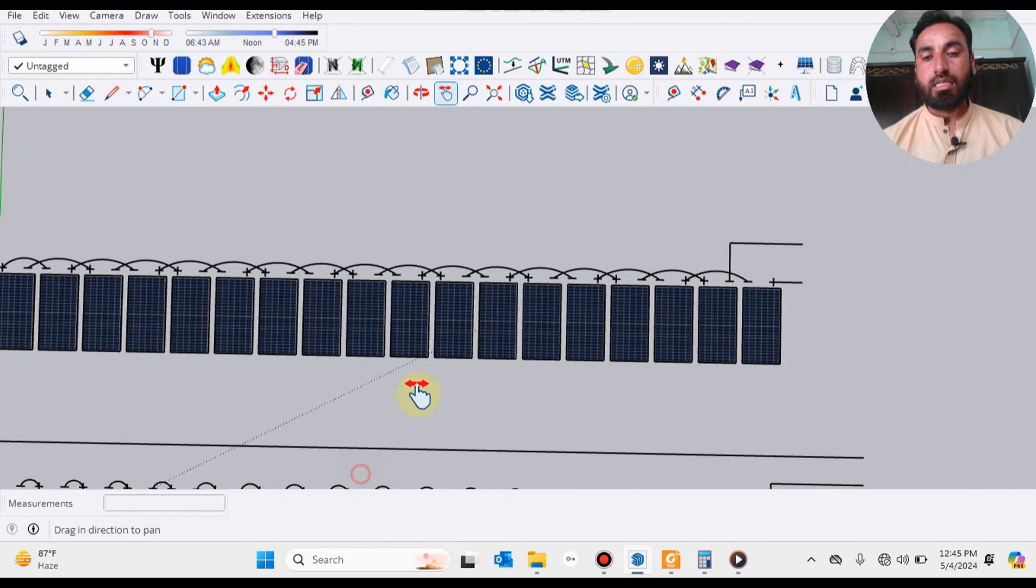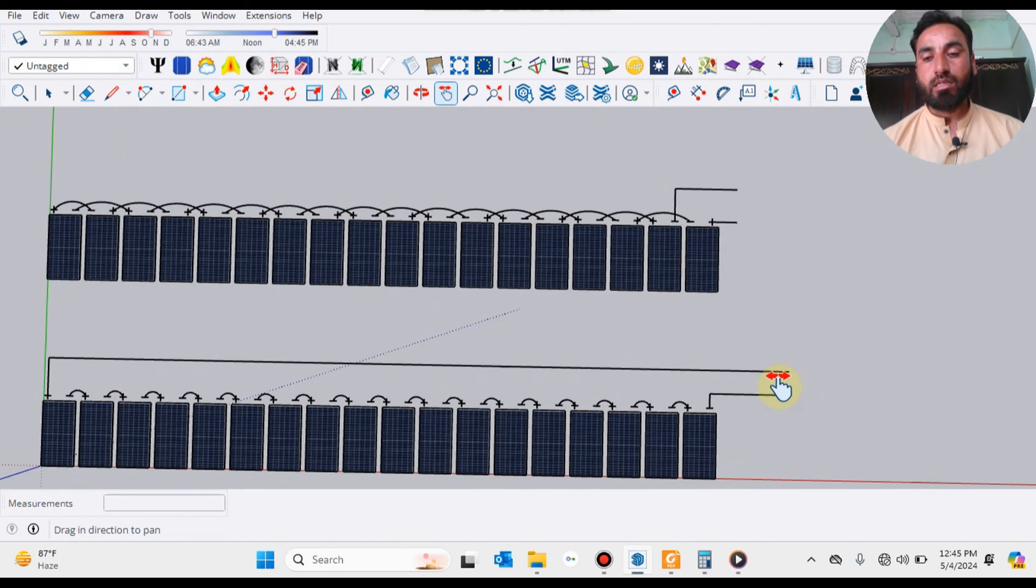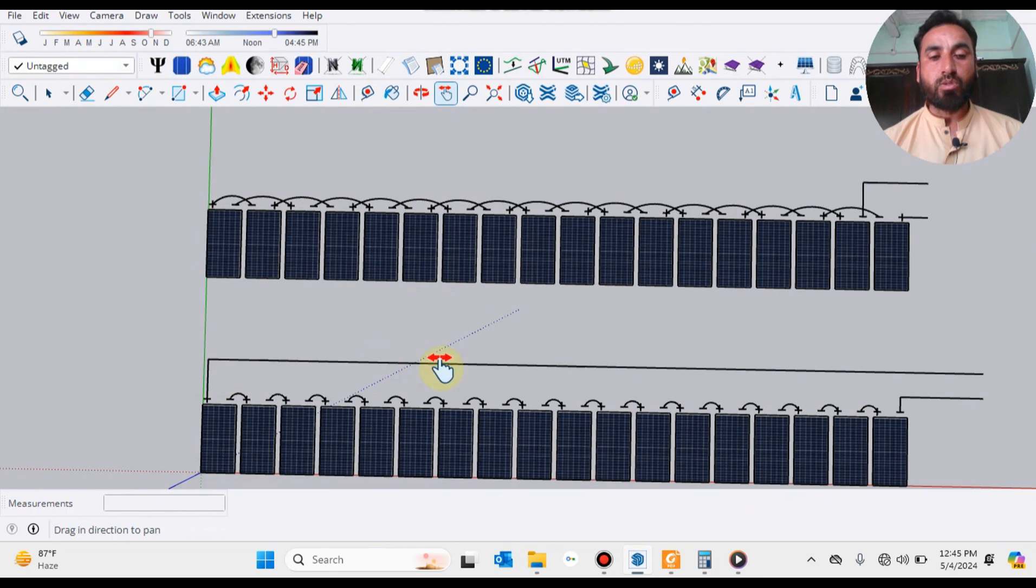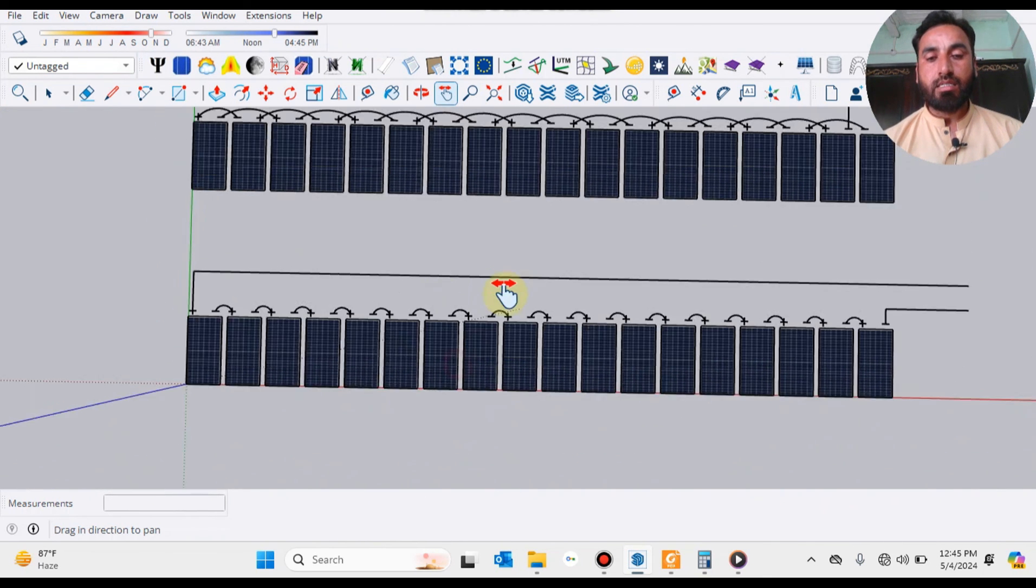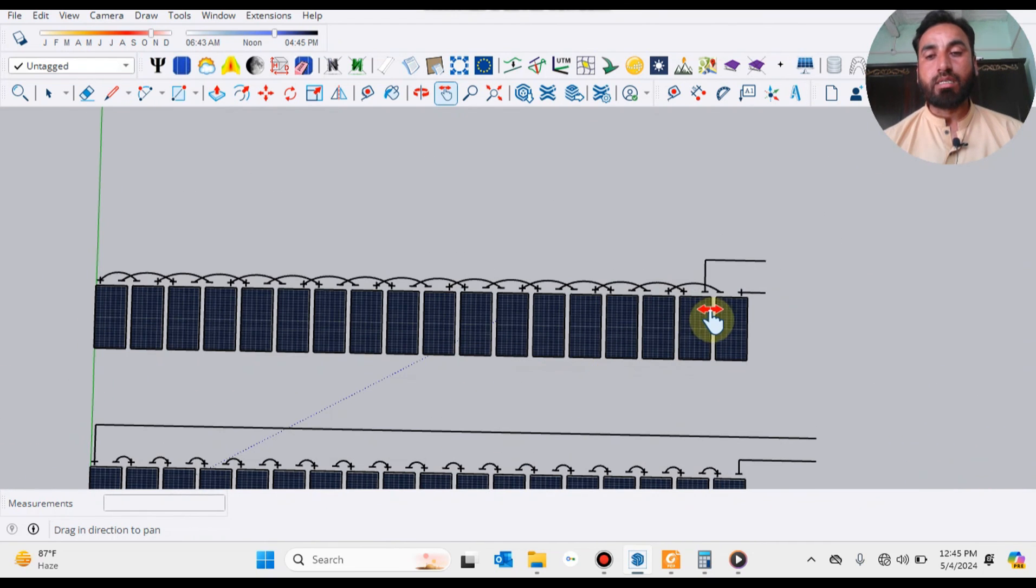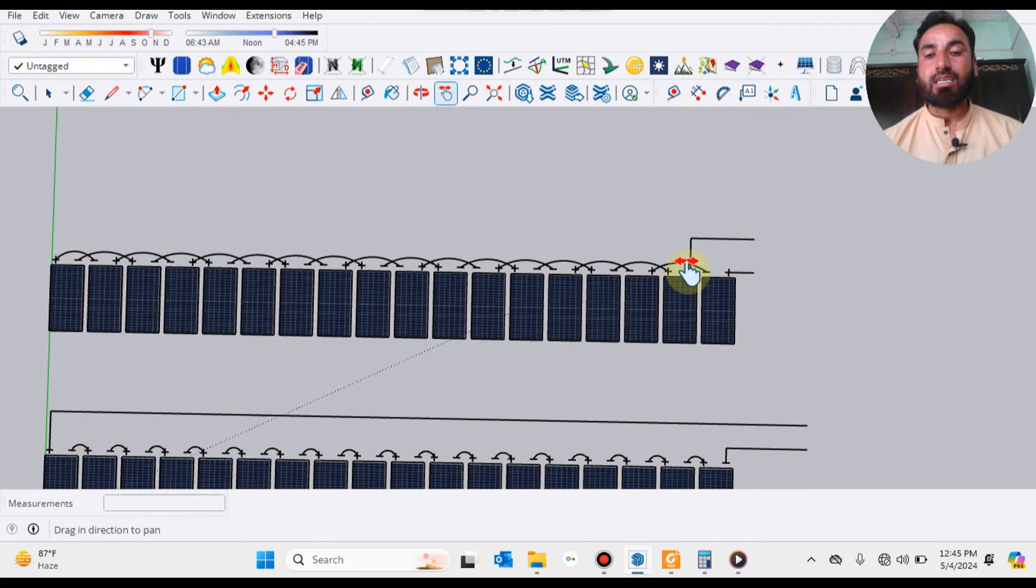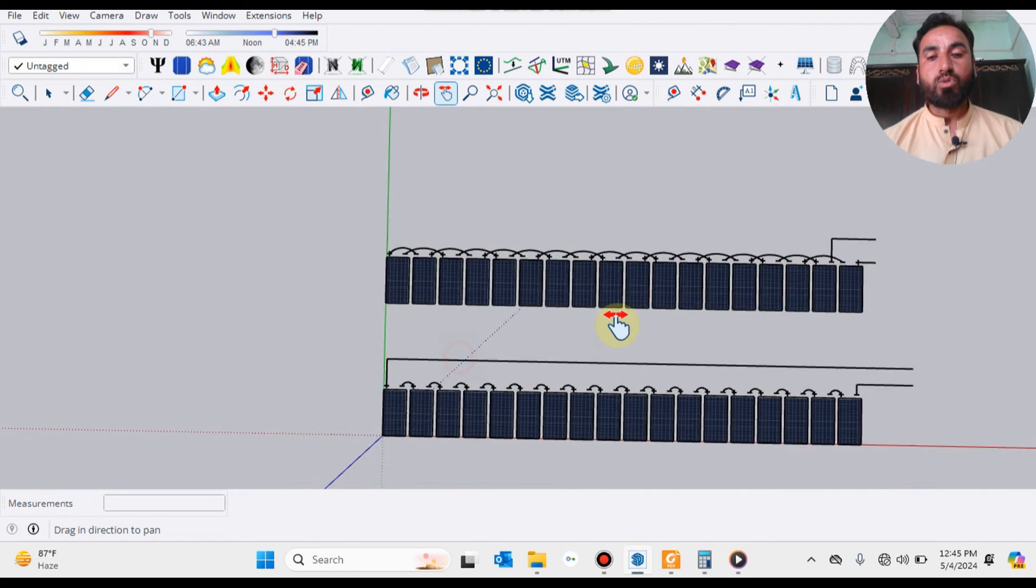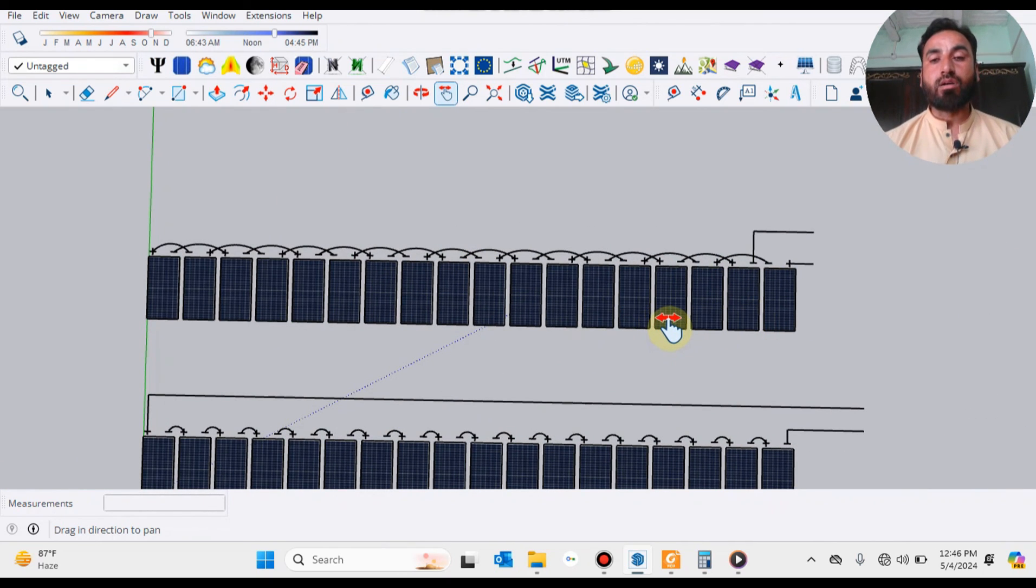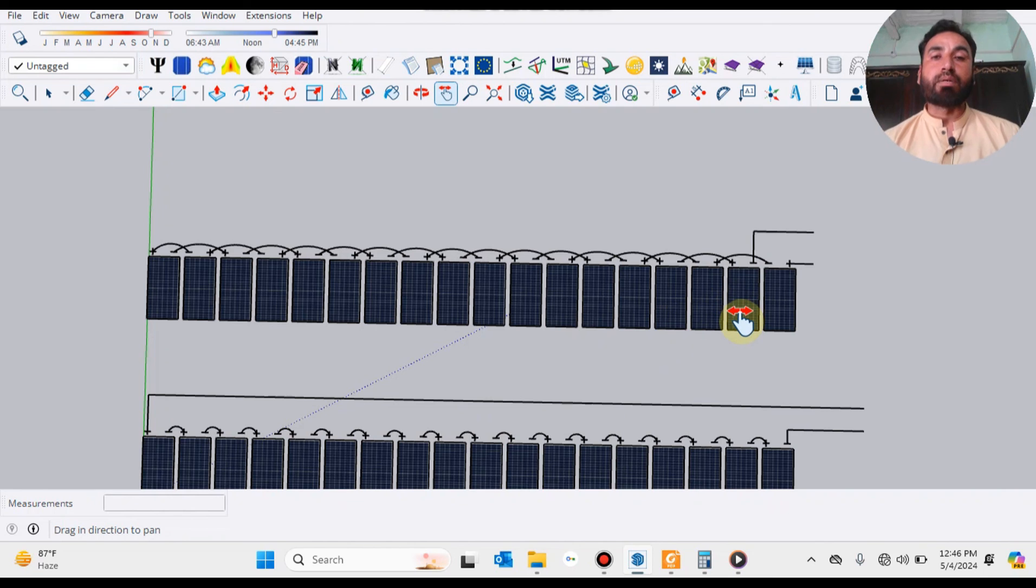Both the ends of the string wiring are inside. Here you can notice only this small piece of DC cable is using here instead of this long DC cable length. In leapfrog jumping, we have saved our DC cable. It's very easy and very efficient method of series wiring, and I must refer this to implement in your megawatt project.